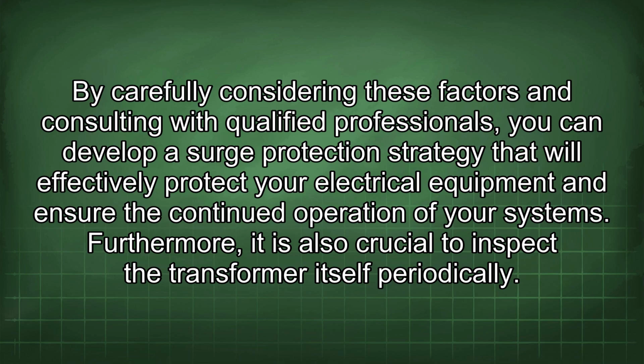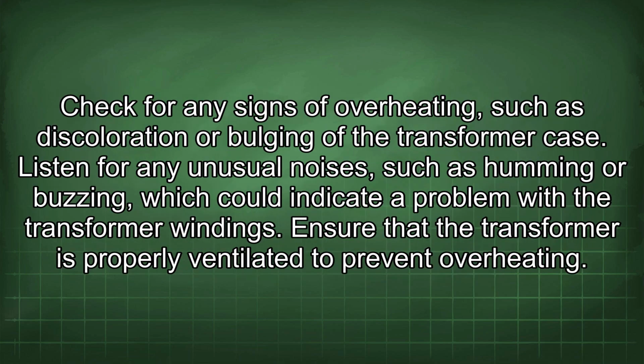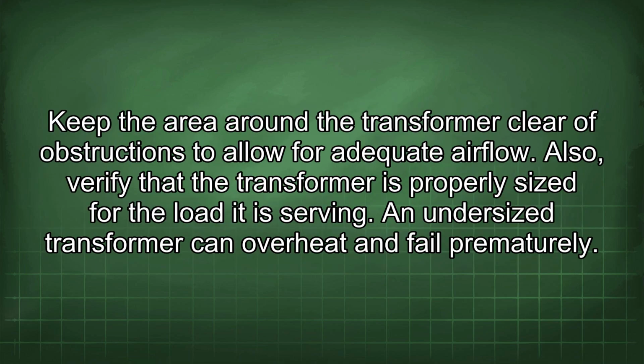Furthermore, it is also crucial to inspect the transformer itself periodically. Check for any signs of overheating, such as discoloration or bulging of the transformer case. Listen for any unusual noises, such as humming or buzzing, which could indicate a problem with the transformer windings. Ensure that the transformer is properly ventilated to prevent overheating. Keep the area around the transformer clear of obstructions to allow for adequate airflow.